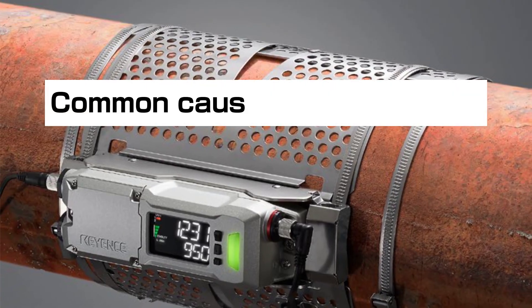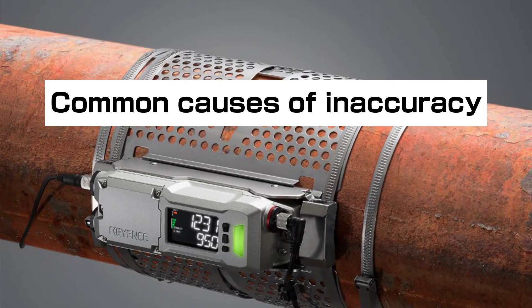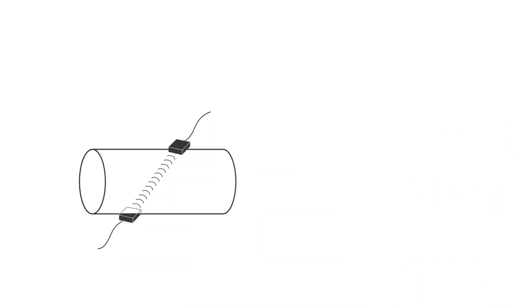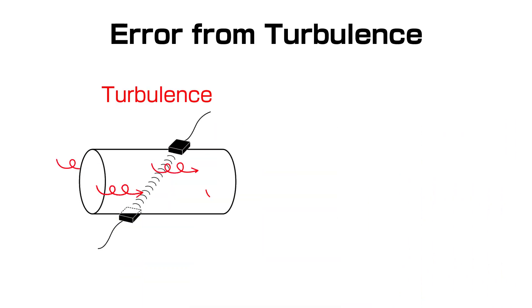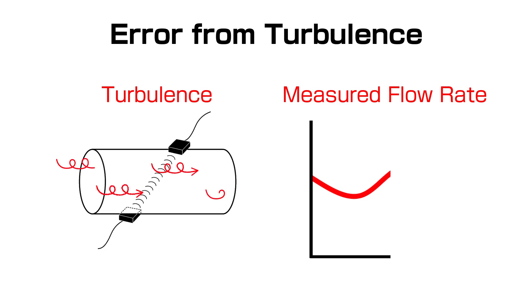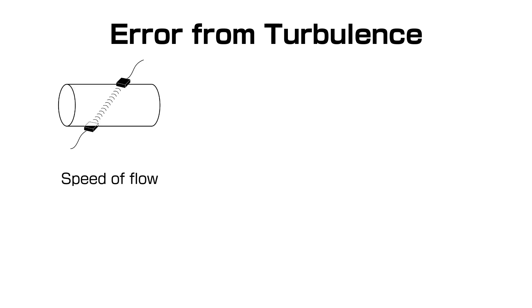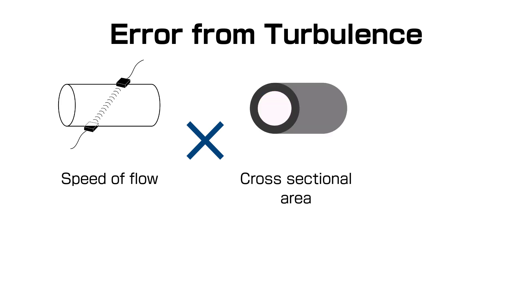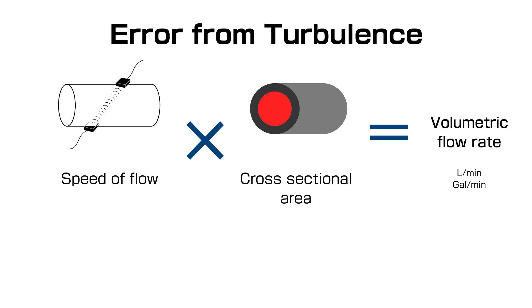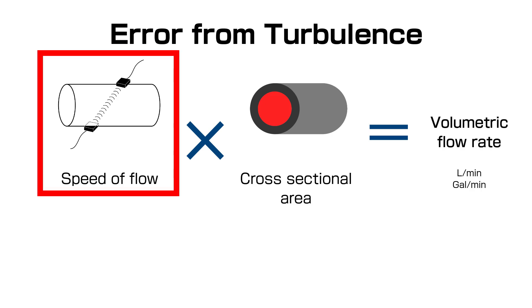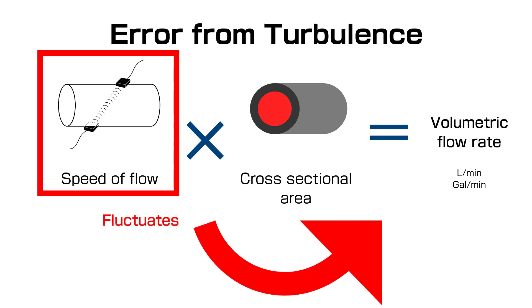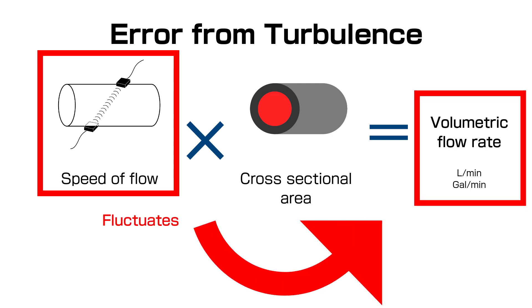First, we'll discuss some common reasons why you would see inaccuracies in a clamp-on ultrasonic flow meter. If the flow inside the pipe is very turbulent, the flow rate reading will typically begin to fluctuate. This is because ultrasonic flow meters detect the speed at which liquid travels through the pipe and multiply this speed by the internal cross-sectional area of that pipe — this is how they arrive at a volumetric flow rate. If the meter detects that fluid speed is fluctuating due to turbulence, the flow rate reading will fluctuate as a result.